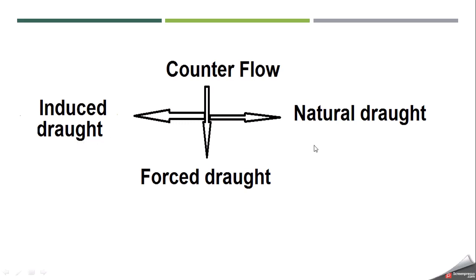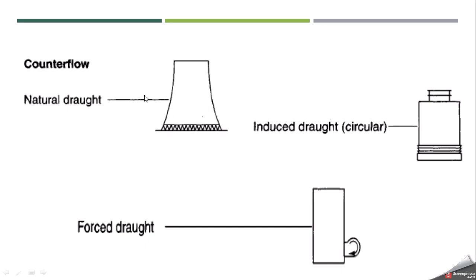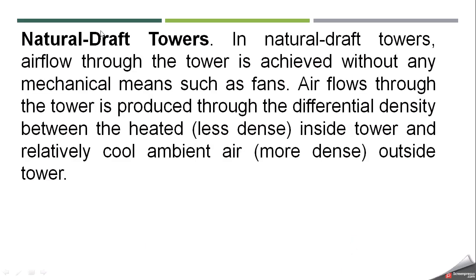Similarly, in counter flow there are three types: natural draft, induced draft, and forced draft. In natural draft towers, airflow is achieved without any mechanical means such as fans. Airflow is produced through the differential density between the heated air inside the tower — which is less dense — and the relatively cold ambient air outside. When air absorbs heat from the hot water, it becomes hotter and less dense, causing it to move upward.